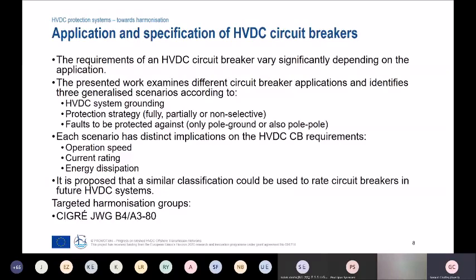The work presented in the technical work packages in promotion has shown that there are several different scenarios that you might want to use distinct circuit breaker configurations or types for on an HVDC system. Each scenario has different implications in operation speed, current rating, energy dissipation, for example. It's proposed that this sort of classification could be useful to rate circuit breakers in future HVDC systems.